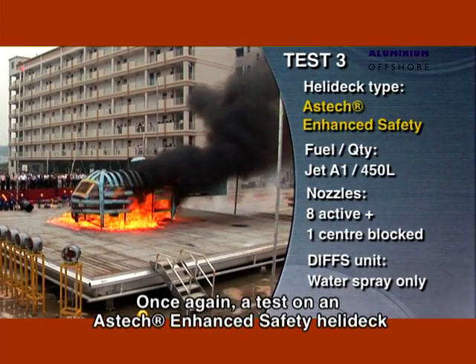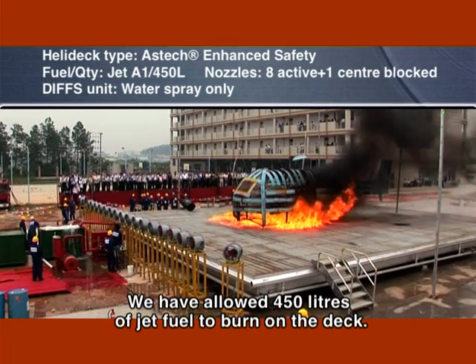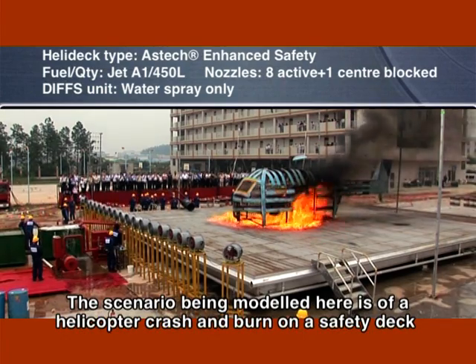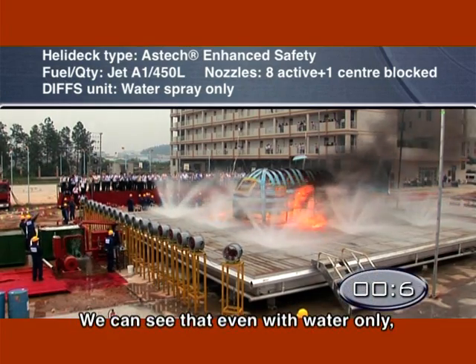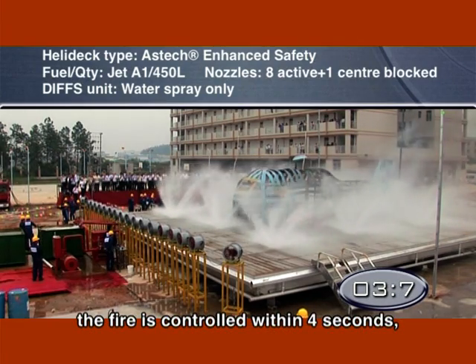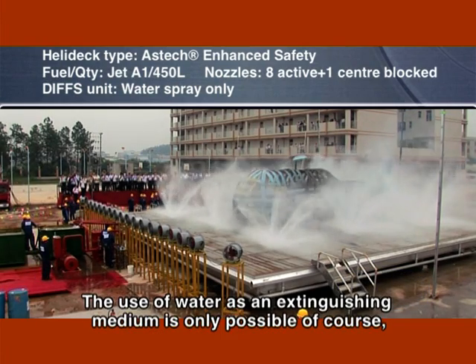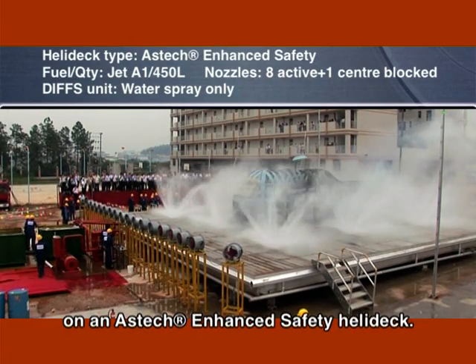Once again, a test on an Astech® Enhanced Safety helideck with passive fire-retarding system. We have allowed 450 litres of jet fuel to burn on the deck. The scenario being modelled here is of a helicopter crash-and-burn on a safety deck equipped with a water spray DIFFS unit. We can see that even with water only, the fire is controlled within four seconds, which is a fantastic result. The use of water as an extinguishing medium is only possible on an Astech® Enhanced Safety helideck.